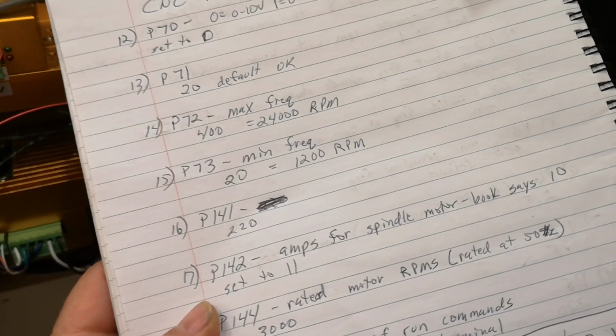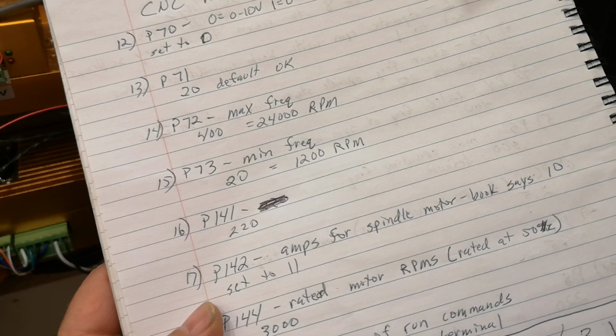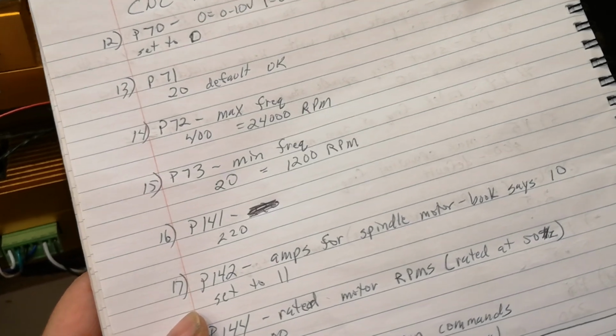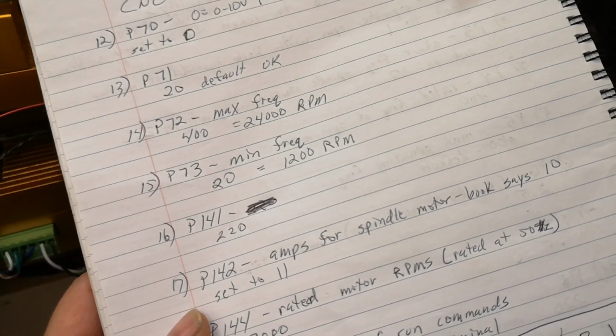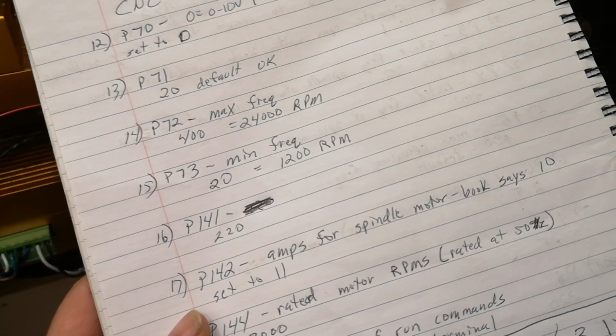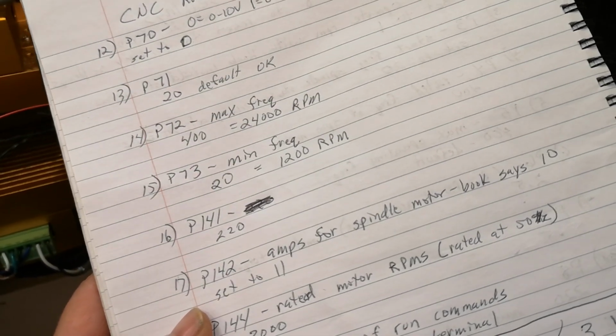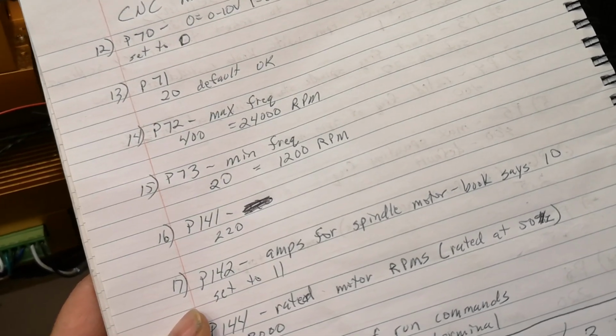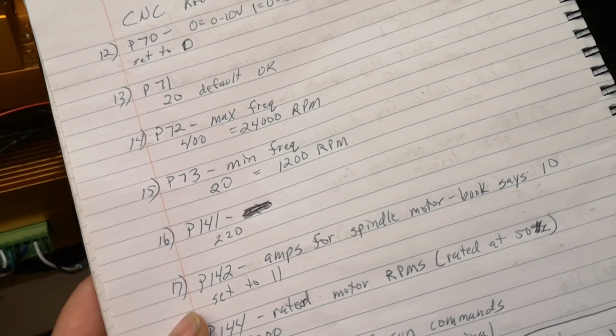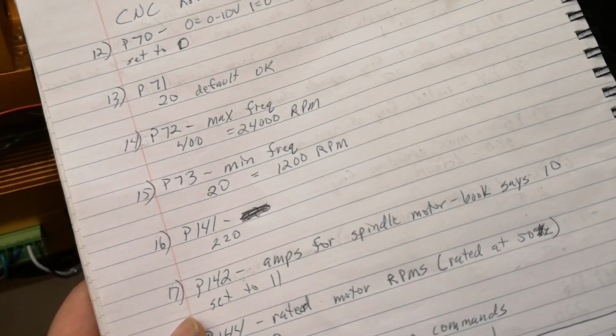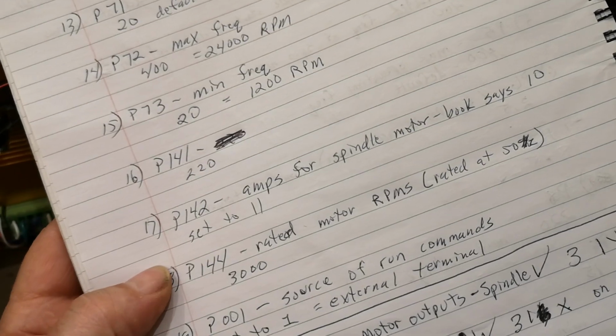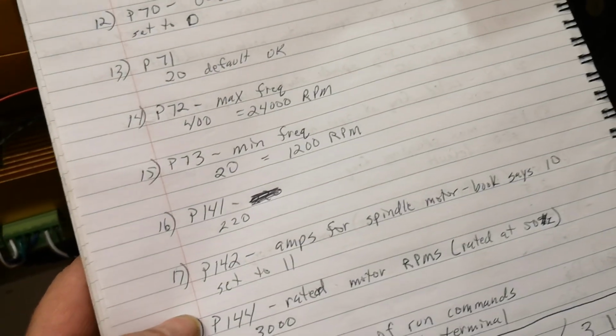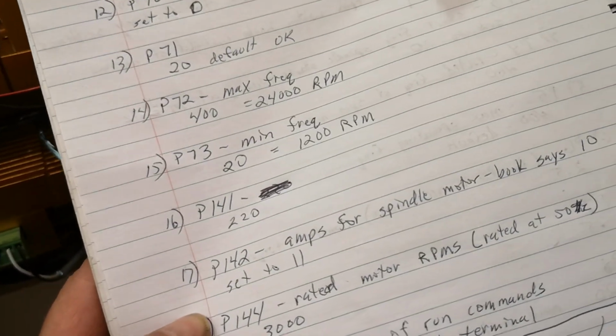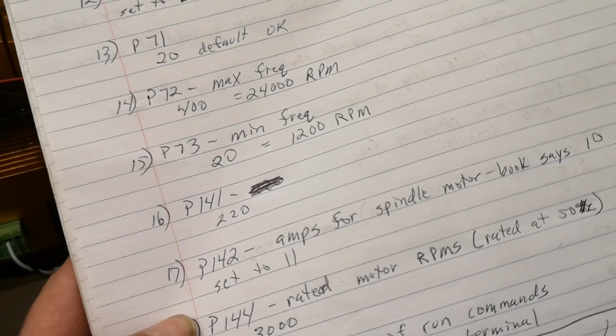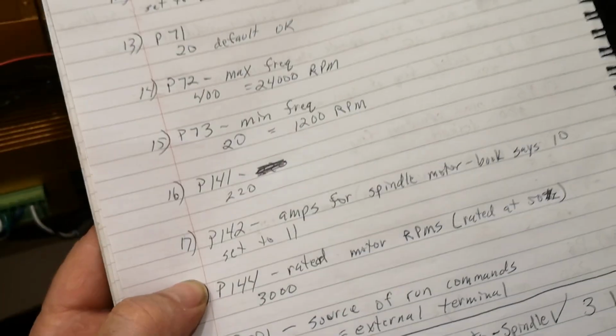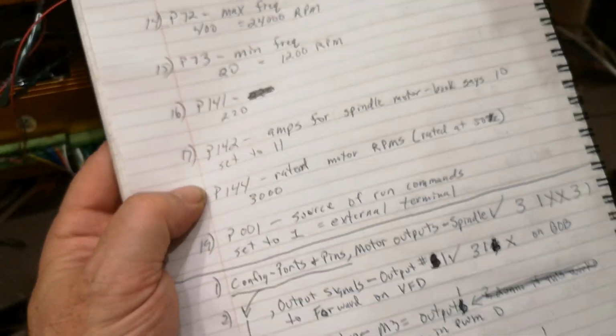P72 and P73 are important. That sets your minimum and max. I've got my maximum RPM at 24,000 and my minimum at 20 hertz. That gives me 1200 RPMs, which I think is what they say these motors don't want to run any lower than 1000 or 1500. You know, that's on the low side of what they recommend or something like that. I think I read it somewhere.